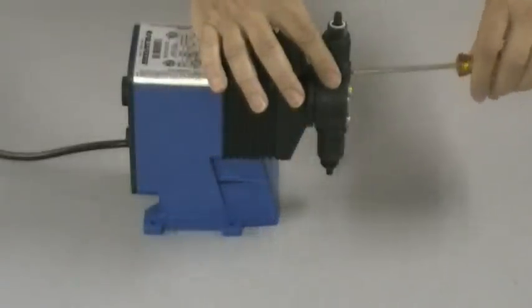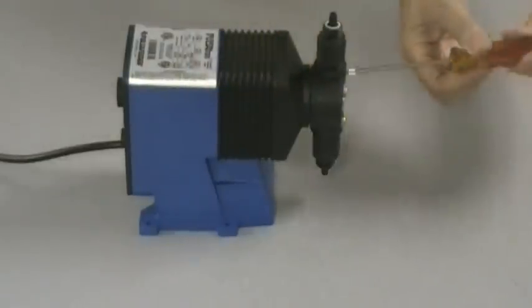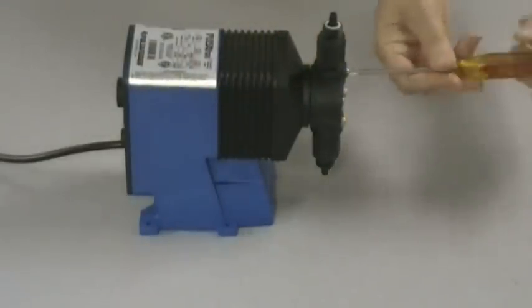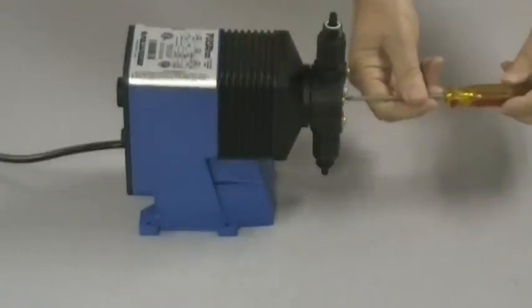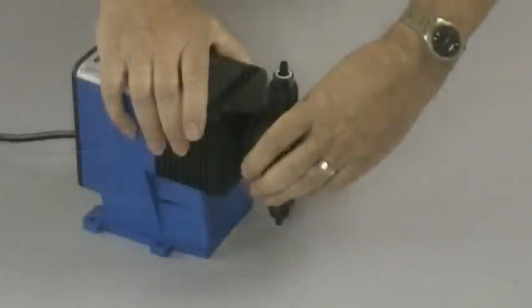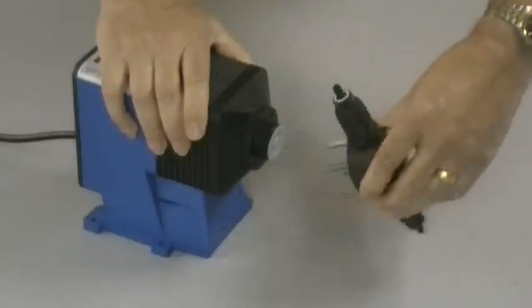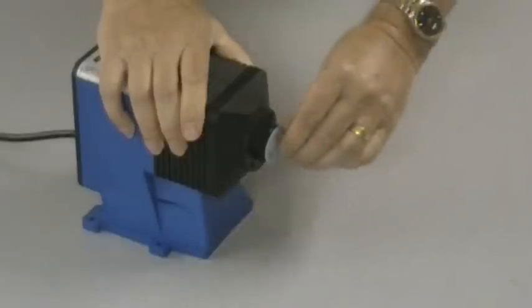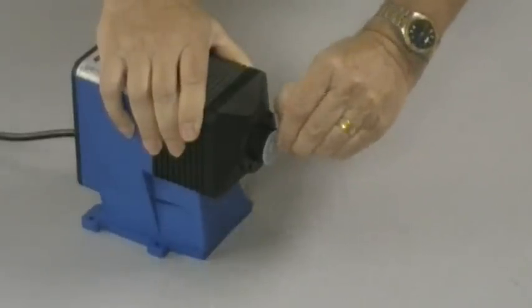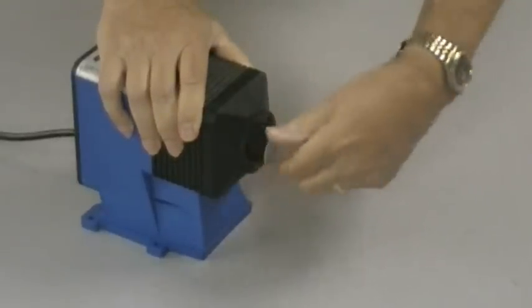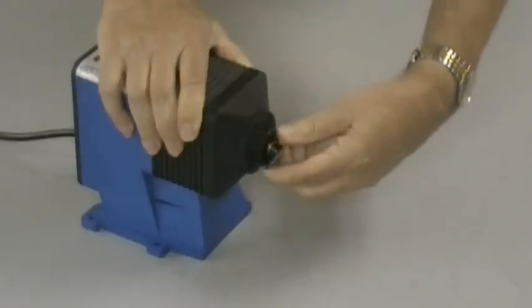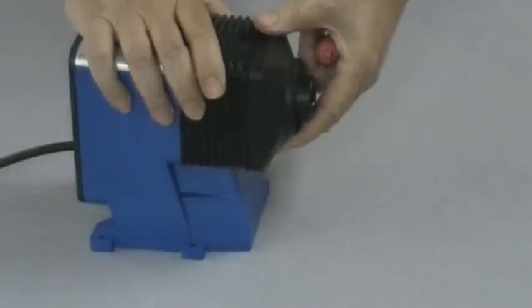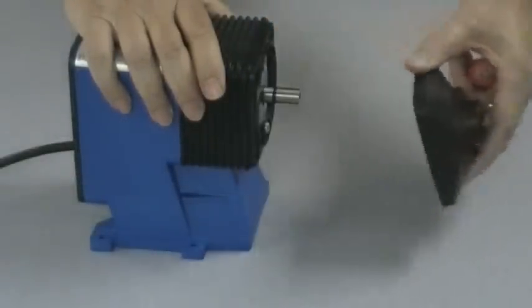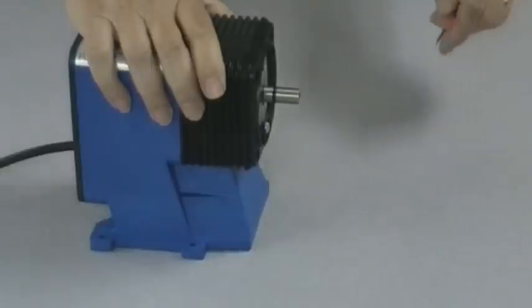The first step in replacing the KOP kit is to remove the wet end. Once the head screws are loose, remove the head from the pump. Then remove the diaphragm by grasping one edge and rotating it counterclockwise to unscrew the diaphragm. Now we are ready to remove the adapter plate. It pulls directly off, away from the shaft.